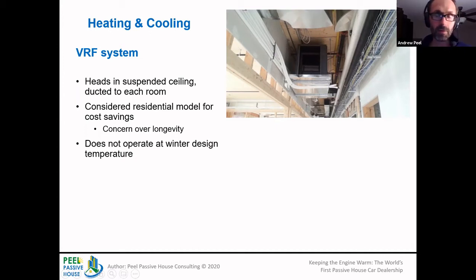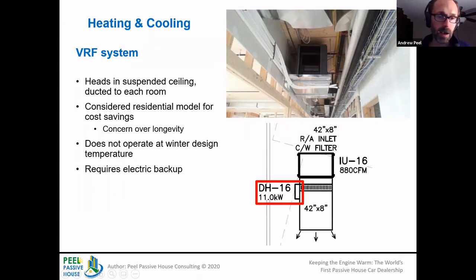And unfortunately, this heat pump system doesn't work at the winter design temperature, despite some assurances from the manufacturer. Engineers weren't confident in that. And so we ended up needing to have electric backup for all the heat pumps. And as we'll see, the system was well oversized, which meant they also had to put in electric backup sized to meet the capacity of the heat pump system, which was much higher. So even the backup system is much higher.